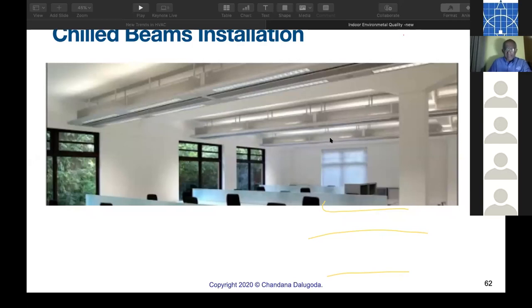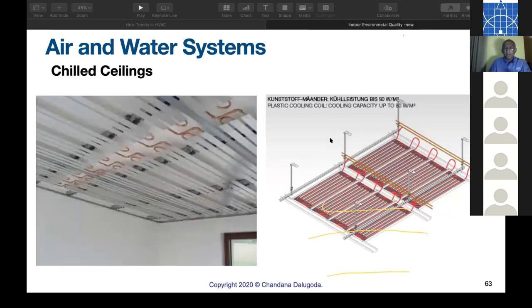These are the chilled ceilings. Same principle. You would think when we install these things, there will be condensation. You might think we have to have an umbrella inside the office. No. Because these are sensible passive cooling equipment. Sensible cooling only. The surface temperature is above the dew point temperature of air, so it is not condensing. Then you will ask, how is the latent heat removed? Now, I'm telling this over and over again.